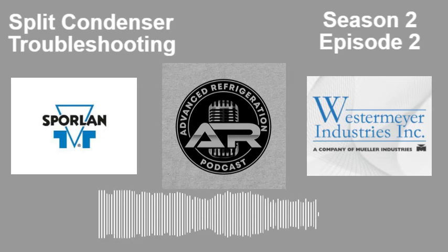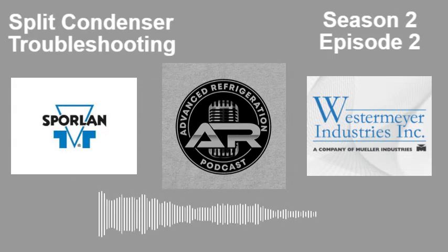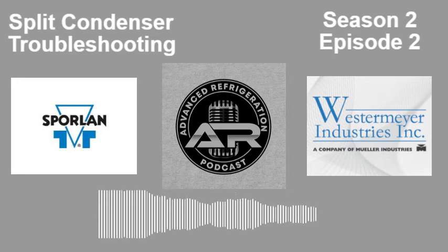the EMS relay. Another thing to watch out for if you guys have stuff that's not splitting or stuff that's going in and out. I see this a lot on Hussmann racks. They do a pressure control override, and Zero Zone does this too. So they do like a pressure control override that hard locks out the split valve. So if it gets, say, 200 pounds or 250 pounds, it's going to override and hard break the power and kill the split valve.